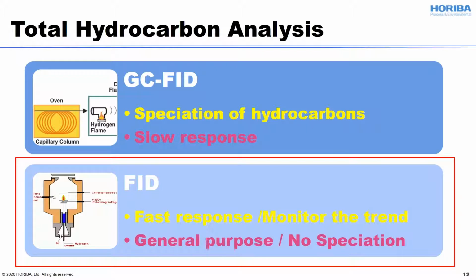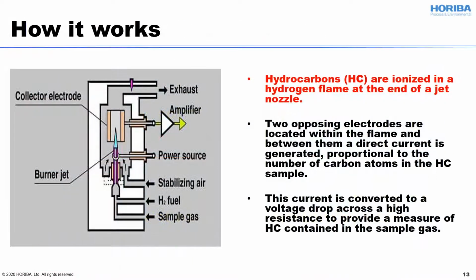Today, we are going to focus on the regular FID and the HORIBA analyzer model MEXA-1170HFID. This slide shows how flame ionization detection works. Sample gas is introduced from a sample inlet and burned in a hydrogen flame at the end of the jet nozzle. During this process, hydrocarbons are ionized in the hydrogen flame. Two opposing electrodes are located within the flame. Between them, a direct current is generated and it is proportional to the number of carbon atoms in the hydrocarbon sample. This current is converted to a voltage drop across a high resistance to provide the measurement of hydrocarbon contained in the sample gas.